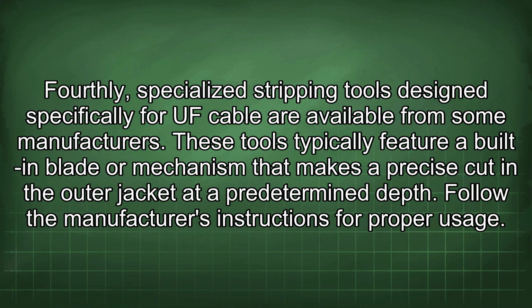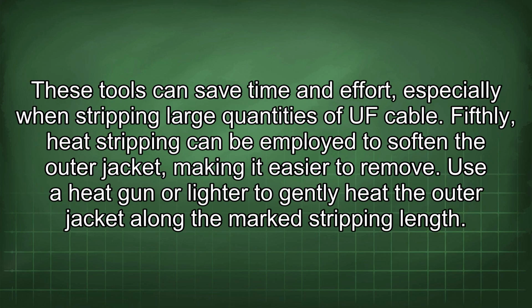Fourthly, specialized stripping tools designed specifically for UF cable are available from some manufacturers. These tools typically feature a built-in blade or a mechanism that makes a precise cut in the outer jacket at a predetermined depth. Follow the manufacturer's instructions for proper usage. These tools can save time and effort, especially when stripping large quantities of UF cable.